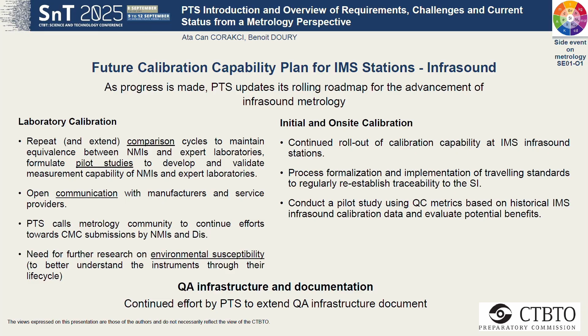For the initial and on-site calibration, the rollout of calibration capabilities at infrasound stations will continue. The process for using traveling standards will be formalized and implemented to regularly establish traceability to the SI units. And a pilot study will be conducted using QC metrics based on historical IMS infrasound calibration data to evaluate potential benefits.